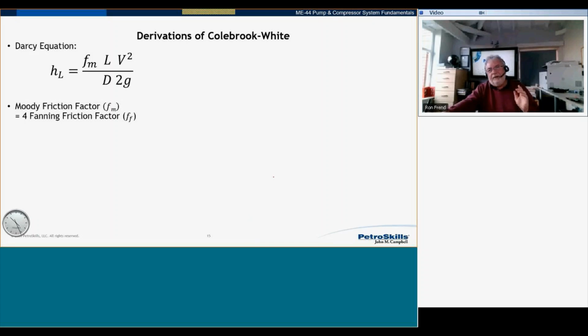Now, remember back to your days at school. Your chemical engineers and your mechanical engineers are all familiar with this. And remember the story of Monsieur Darcy in France a few hundred years ago. He figured out a way of piping fresh water to his village. And what he came up with was this. The head loss, not pressure loss, head loss, is a friction factor. In this case, we're using the Moody friction factor, so it's f subscript M. If you say f subscript F, that's the Fanning friction factor. They're identical apart from a factor of 4.